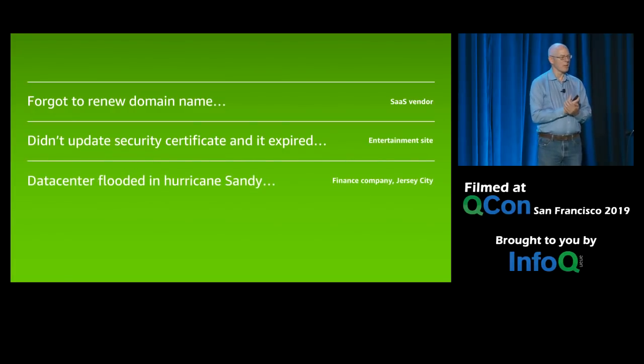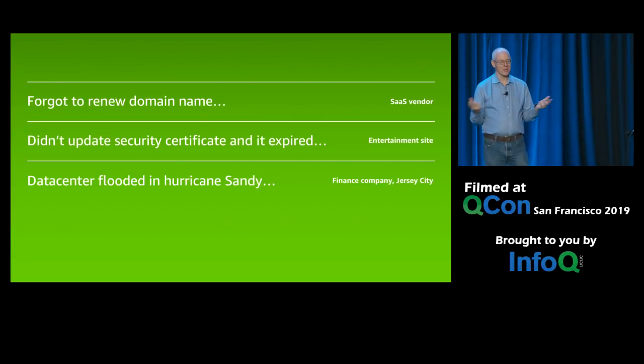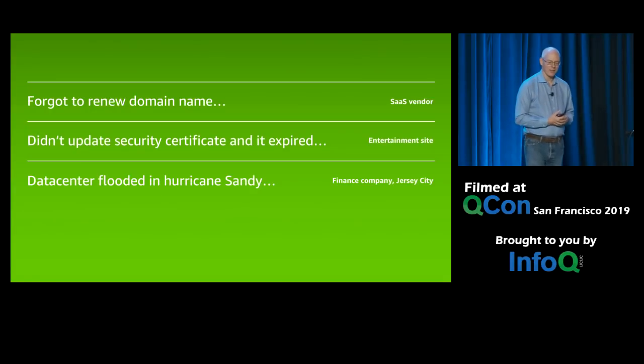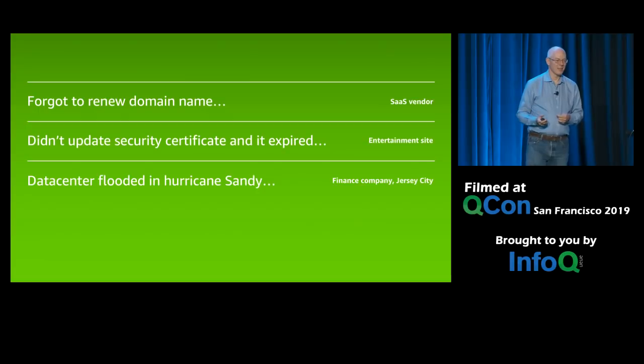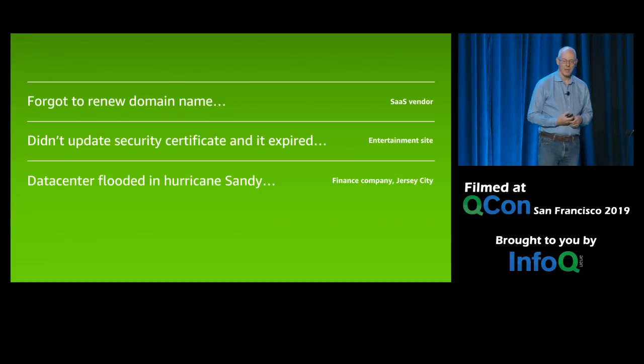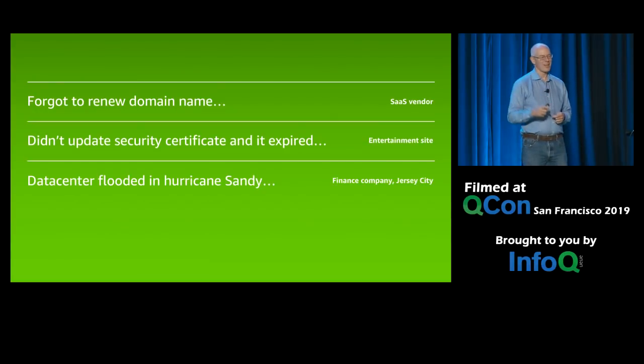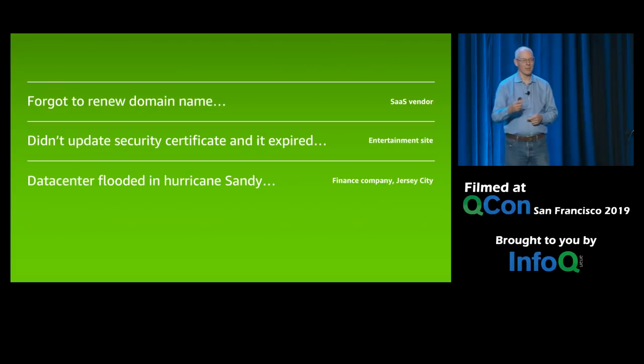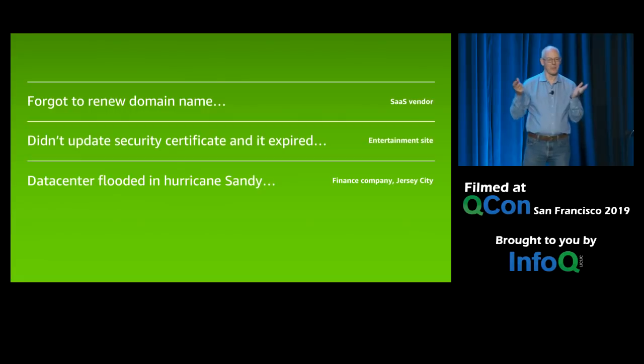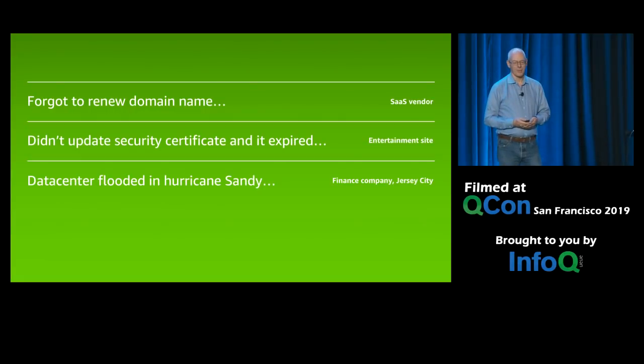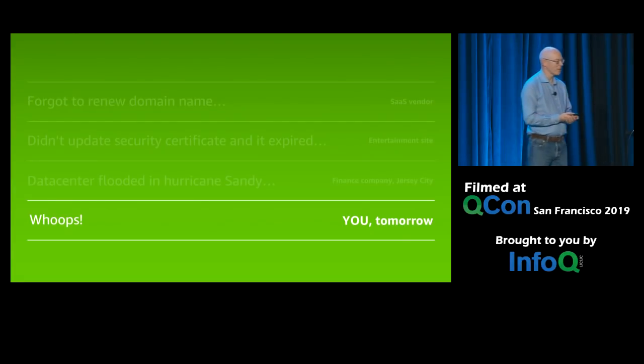Computers don't work underwater — very sad. When the water goes away, they're full of sand, seaweed, and dead fish. A friend of mine had a lovely time rebuilding a data center that was no longer in a basement in Jersey City. Another trick: don't put the generators in the basement. And don't put the fuel supply for the generators in the basement either. Try to keep stuff above flood level if possible.